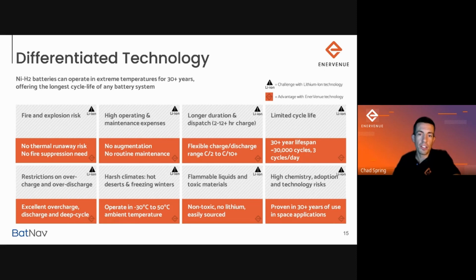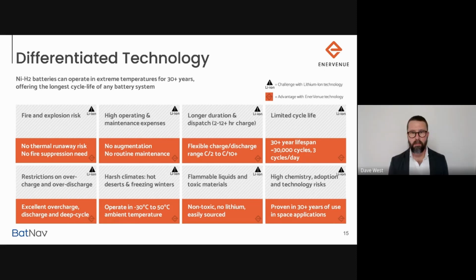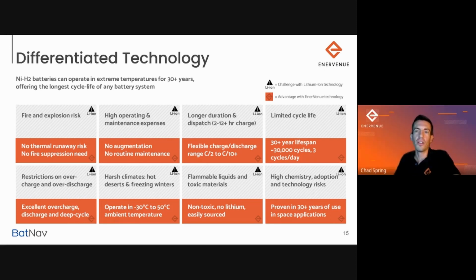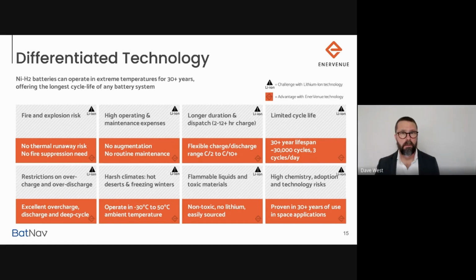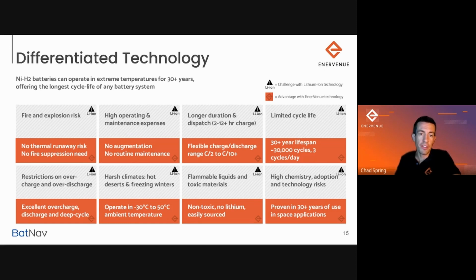It doesn't require a certain resting state of charge. It ships at 0%, so that allows a lot of flexibility. And it has a really wide operating temperature range, -30 to 50 C, without heating or air conditioning. So you combine no fire suppression, no heating, no air conditioning - your balance of system is very minimal, very low aux loads. It all plays into the total cost of ownership puzzle.